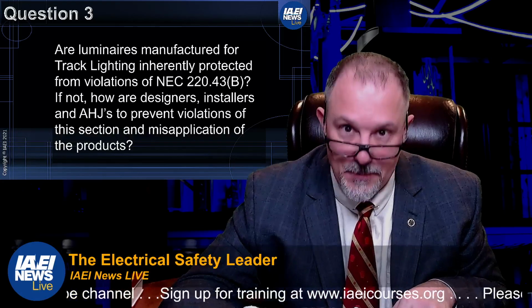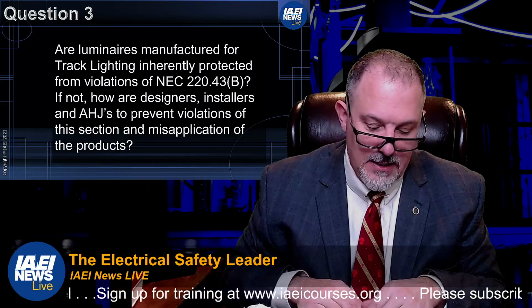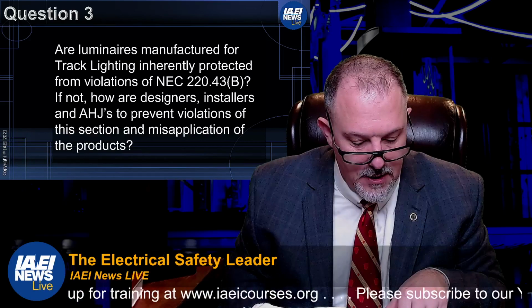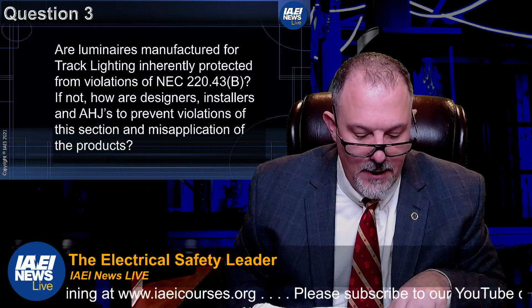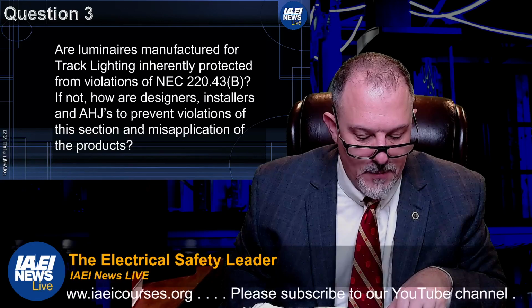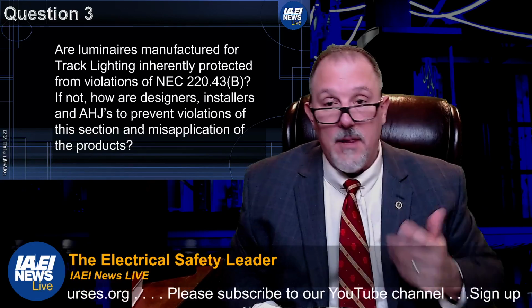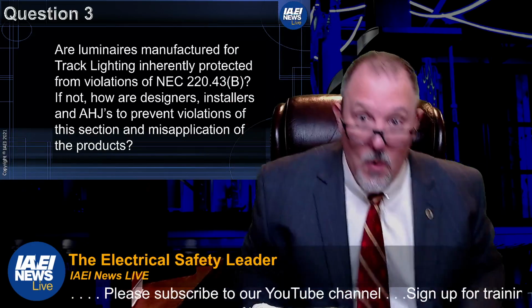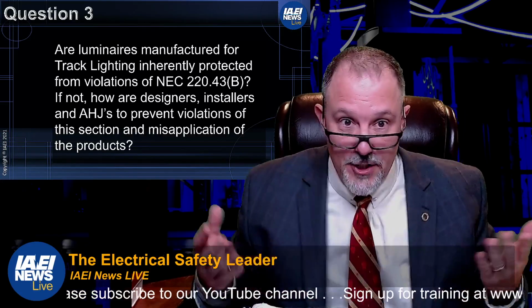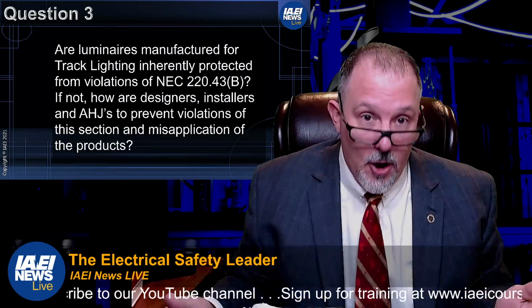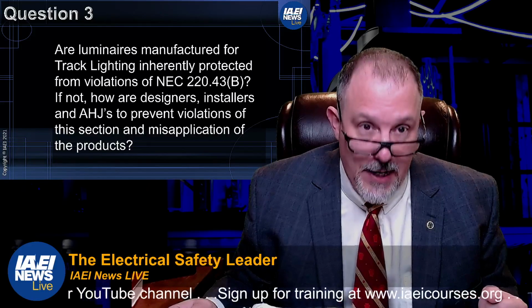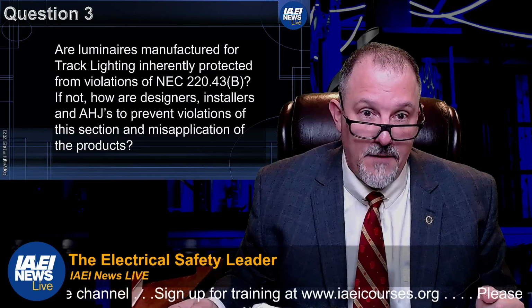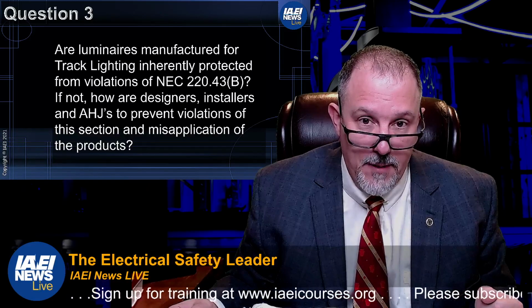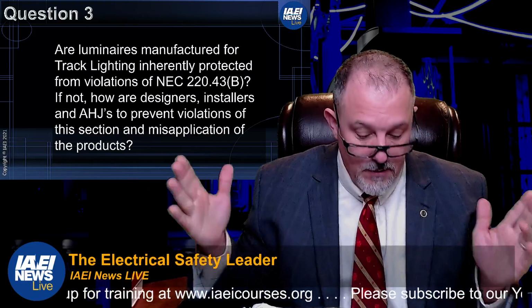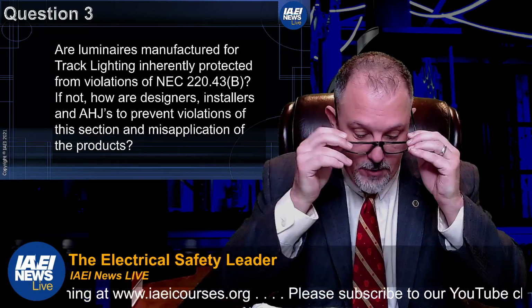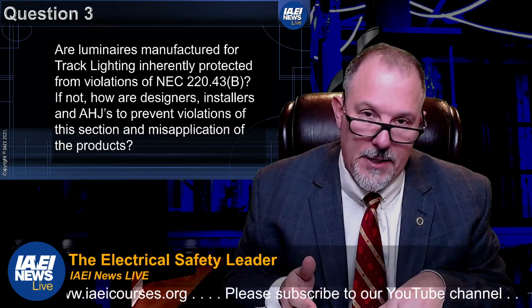There is an exception. If the track lighting is supplied through a device that limits the current to the track, the load shall be permitted to be calculated based upon the rating of the device used to limit the current. All right, so this question says, are luminaires manufactured for track lighting inherently protected from the violations of 220.43(B)? So my thought, to remember, 220.43(B) is a load calculation.